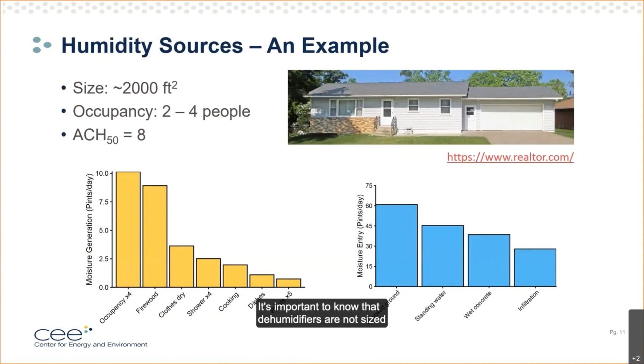It's important to know that dehumidifiers are not sized to meet loads of hundreds to thousands of pints. So the first thing we could conclude is that dehumidifiers are not for dealing with liquid water, whether that's coming up through the ground or a leaky foundation. They might deal with it temporarily, but the size of typical consumer equipment is more in line with occupancy-based loads and infiltration-based loads.